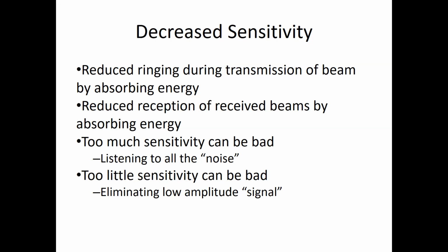They call that the reject. And we'll talk about this with receiver functions, but our machine is rejecting things. And so there's a certain level of rejection that we aim for. Too sensitive, we're going to not reject enough of the low level echoes. High sensitivity, we're going to see a lot of noise. But if I have too little sensitivity, I'm going to start eliminating some of those low level grays. And sometimes I need to see those.